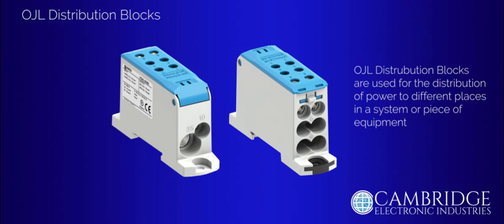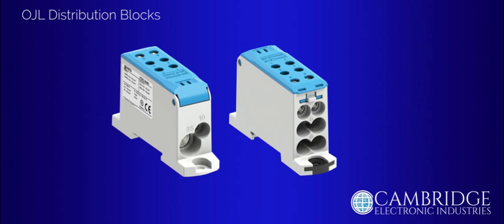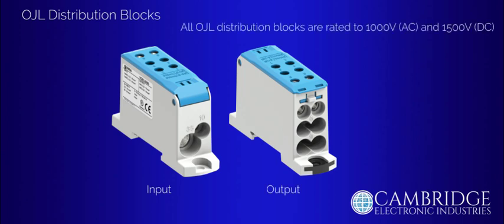They are again a compact module offering efficient use of space in tighter installations and tend to be smaller in comparison to the OTL universal connectors. There are 6 different versions of the OJL distribution blocks, which are generally named in line with their current capability. The blocks are single pole termination blocks with a number of different input and output contacts. All OJL blocks are rated to the 1000 volts AC and 1500 volt DC voltage ratings. It is worth noting that the OJL distribution blocks can accept aluminium cable as their input, but should only be used with copper cable for their outputs.